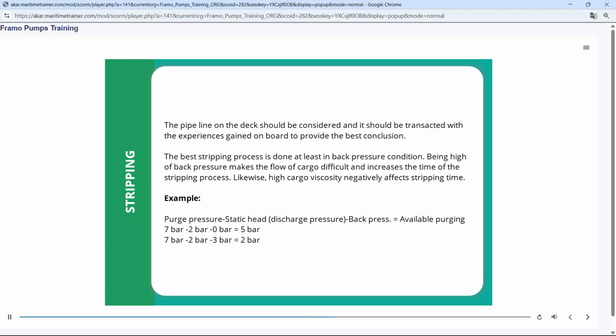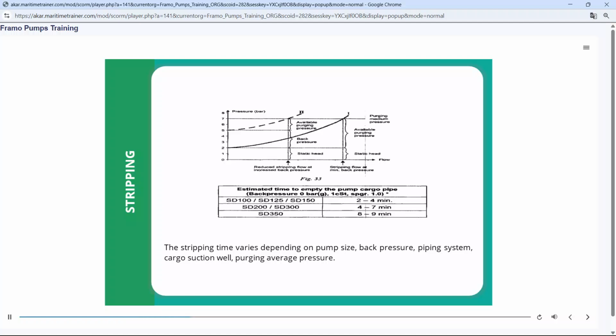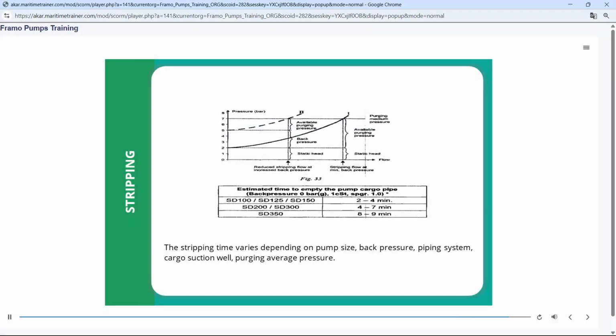For example, purge pressure minus static head minus back pressure equals available purging pressure. 7 bar minus 2 bar minus 0 bar equals 5 bar. 7 bar minus 2 bar minus 3 bar equals 2 bar. The stripping time varies depending on pump size, back pressure, piping system, cargo suction well, and average purging pressure.